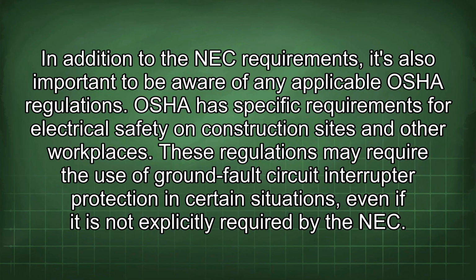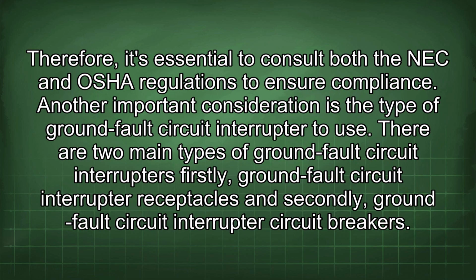In addition to the NEC requirements, it's also important to be aware of any applicable OSHA regulations. OSHA has specific requirements for electrical safety on construction sites and other workplaces. These regulations may require the use of ground fault circuit interrupter protection in certain situations, even if it is not explicitly required by the NEC. Therefore, it's essential to consult both the NEC and OSHA regulations to ensure compliance.